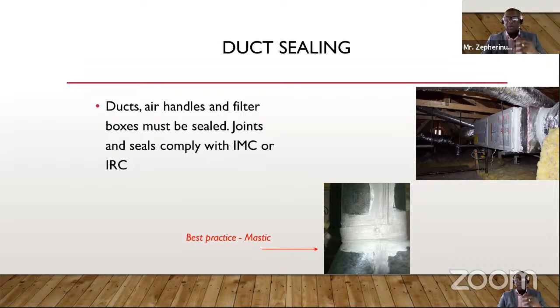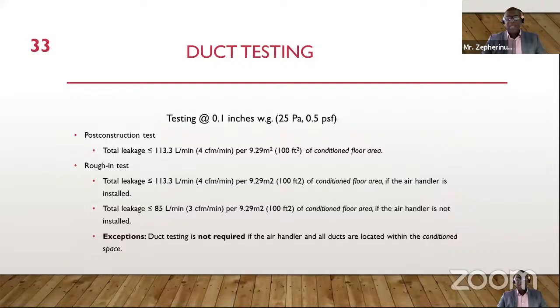So you see that the requirements so far are targeting the hot spots, the energy hot spots in buildings where normally a significant amount of wastage would take place in these areas. And the duct has to be tested as well, based on the testing, how it should be tested. The code provides you with this information. So these are mandatory requirements if you are using the prescriptive compliance options or the simulated performance options for your buildings to demonstrate code compliance.